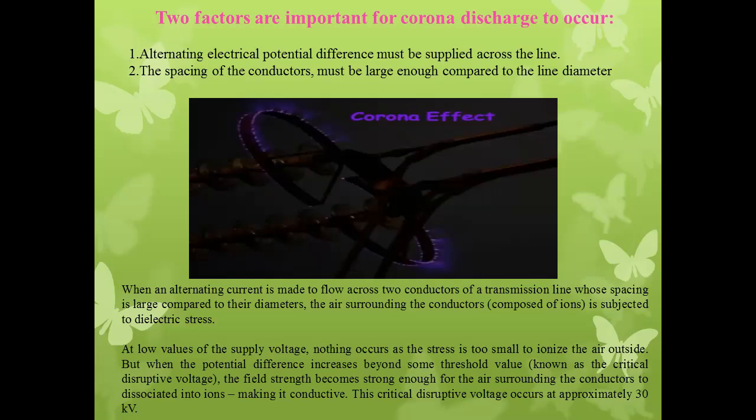Okay, so because of the high voltage stress, the air medium surrounding the live conductor gets ionized. Ion formation will take place, since air consists of oxygen, nitrogen and various other gases. Whenever those gases are subjected to a high electrical field stress, they undergo the ionization process and produce ions.